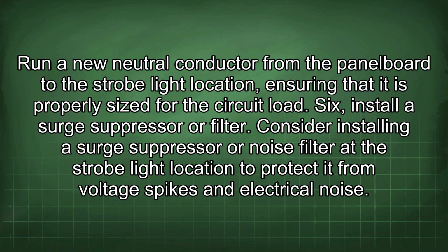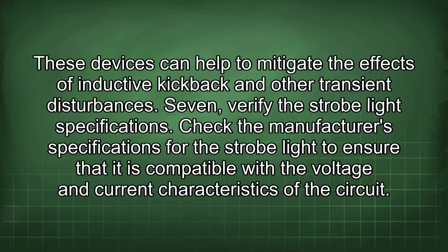6. Install a surge suppressor or filter. Consider installing a surge suppressor or noise filter at the strobe light location to protect it from voltage spikes and electrical noise. These devices can help to mitigate the effects of inductive kickback and other transient disturbances. 7. Verify the strobe light specifications. Check the manufacturer's specifications for the strobe light to ensure that it is compatible with the voltage and current characteristics of the circuit.